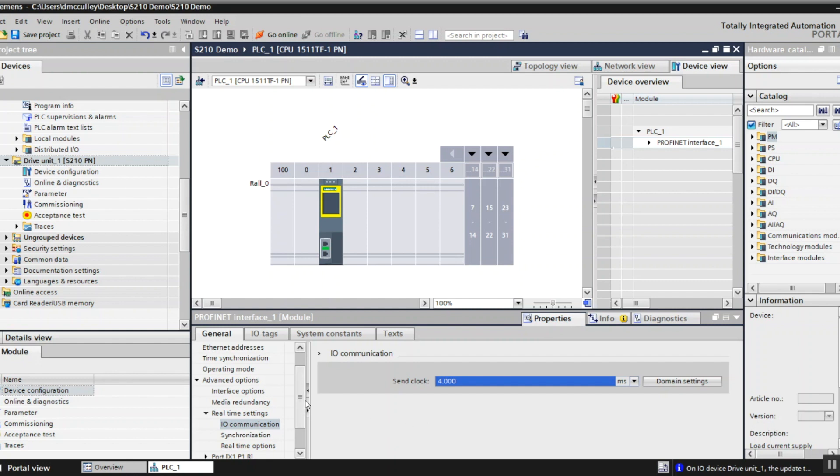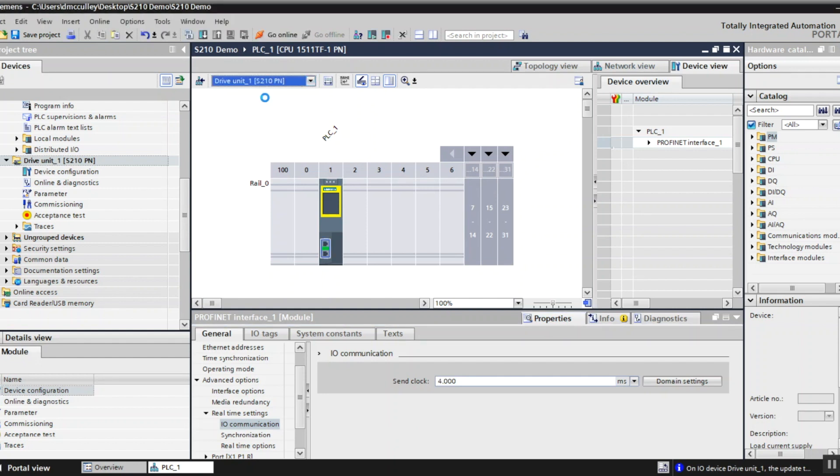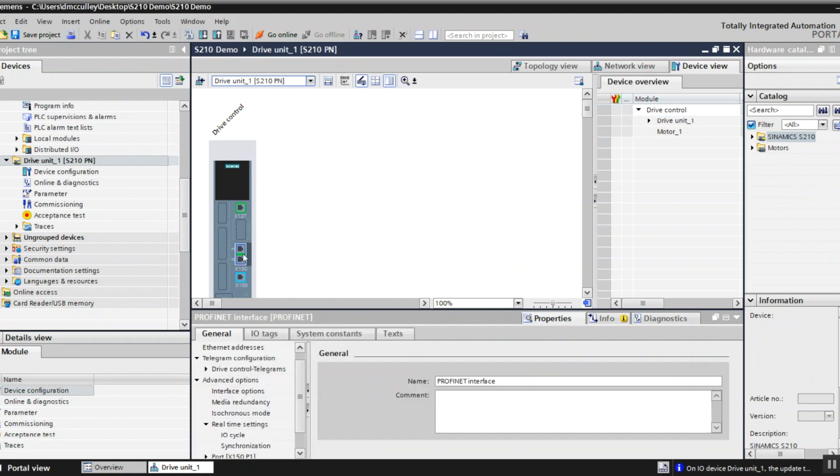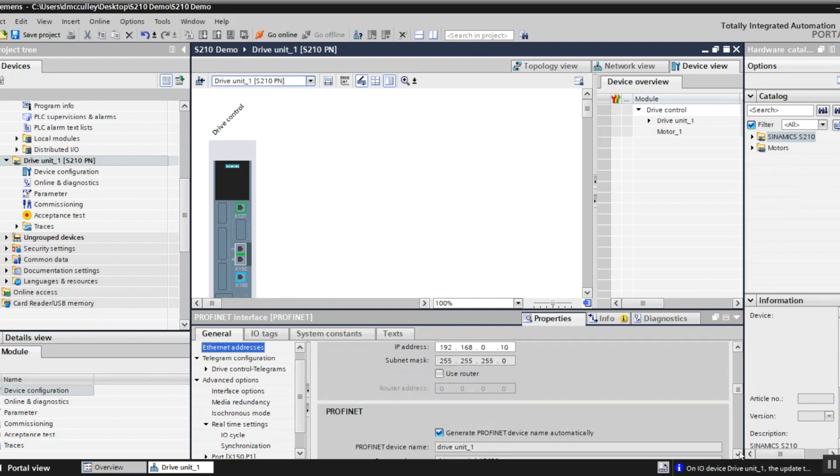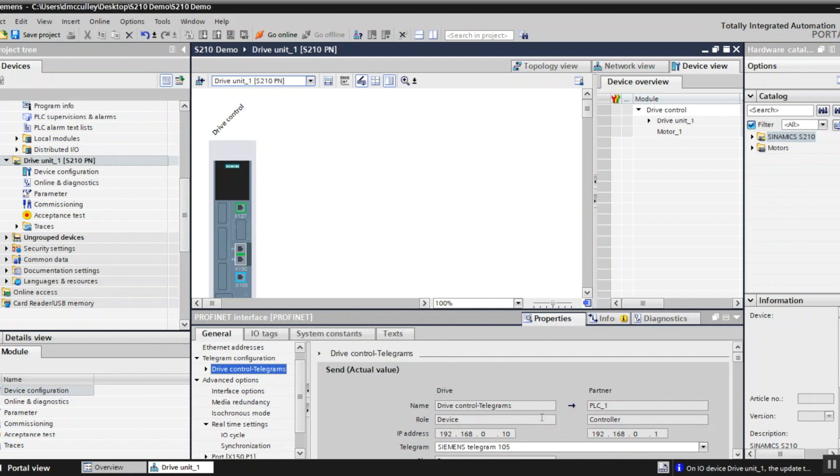I'm done with the PLC so I can drop down and go to the device view of my drive. Click on the Profinet port of it. For the Ethernet address I want to make it a 10 just to show you the change, and I'm going to change it to my S210 for the Profinet device name. Next I have a telegram that defaulted to telegram 105 which is fine.